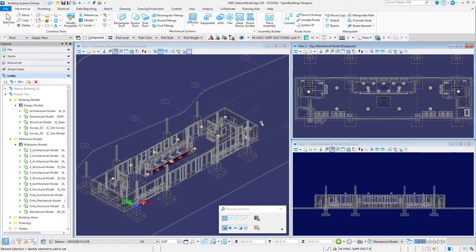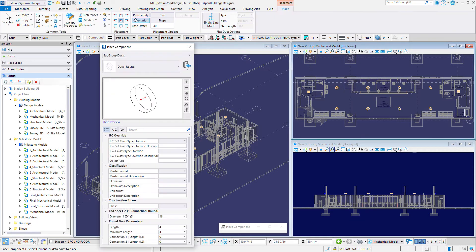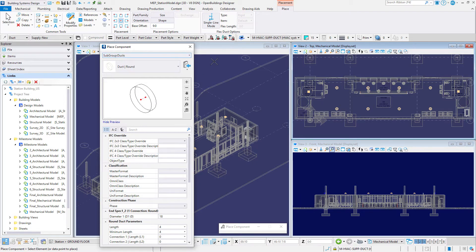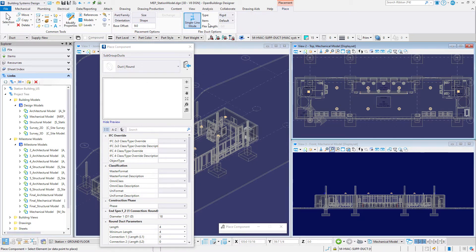Let's select the round duct tool from the mechanical tab. The catalog item will default to duct round. Set the diameter to 18 inches or 450 millimeters. Then toggle on the single-line mode option. The placement justification options are automatically void for the single-line mode.